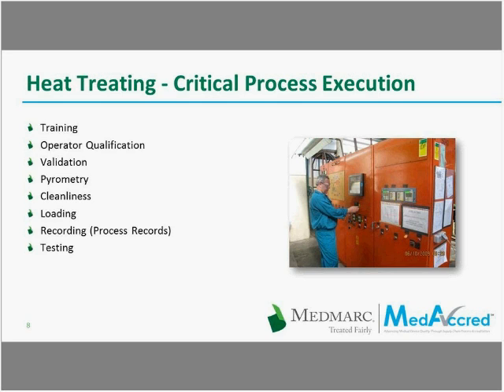The instrumentation used to display and record temperature and periodic tests must ensure all systems operate accurately. Also, the heat treat processor has to provide an appropriately clean environment so as to prevent undue contamination, not only from possible furnace issues but also from the ambient environment and foreign object debris. Processing includes detailed instructions to operators where various facets are controlled on a product-by-product basis — particularly the critical nature of loading parts to assure proper circulation of atmosphere, meeting cooling requirements, and minimizing distortion. Records have to be produced, kept, and monitored to assure all product receives the specified process requirements, and appropriate testing has to be conducted with a record made.